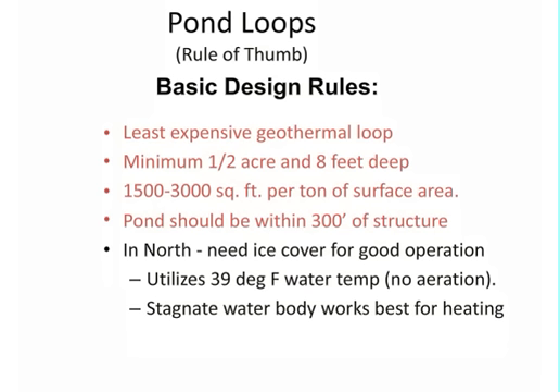1,500 to 3,000 square feet per ton is a good number to use for sizing. It's almost double to 3,000, and that really depends on your load conditions where you're at. You really want to have that pond within about 300 feet of that structure, because by the time you've achieved entrance into that pond, you could nearly have your ground loop in. You also start running into some pumping and purging issues when you have exceedingly long supply and return lines.